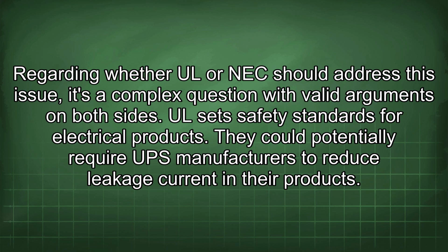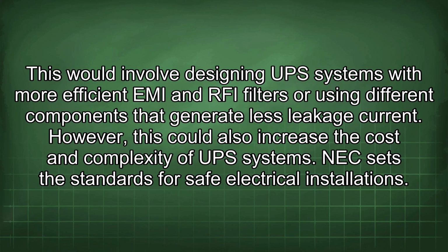Regarding whether UL or NEC should address this issue, it's a complex question with valid arguments on both sides. UL sets safety standards for electrical products. They could potentially require UPS manufacturers to reduce leakage current in their products. This would involve designing UPS systems with more efficient EMI and RFI filters or using different components that generate less leakage current. However, this could also increase the cost and complexity of UPS systems.